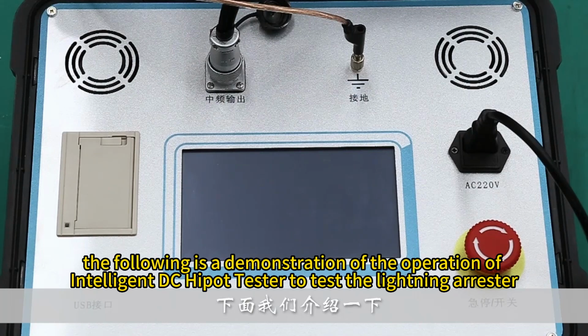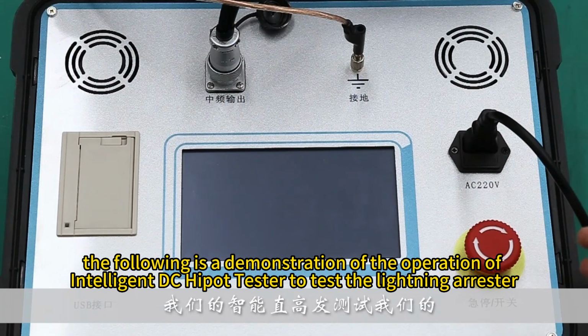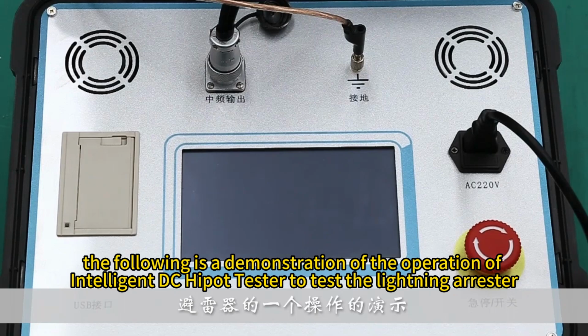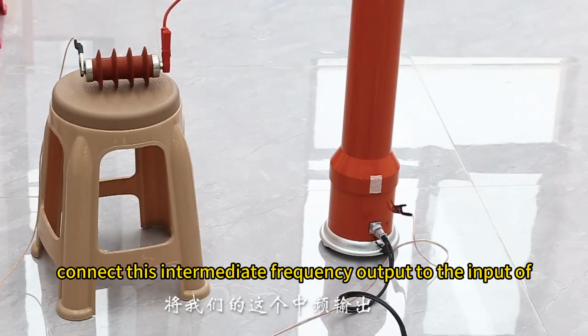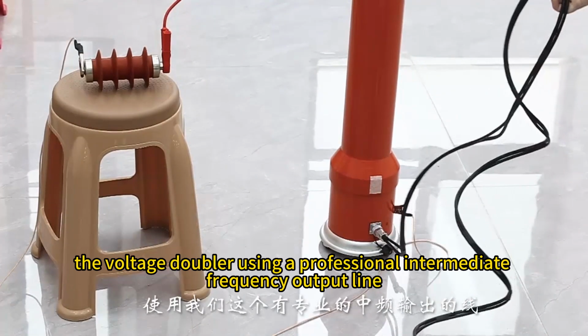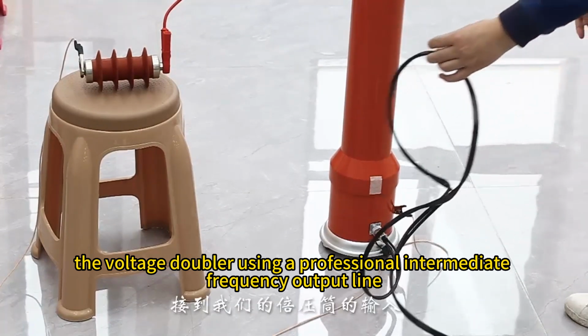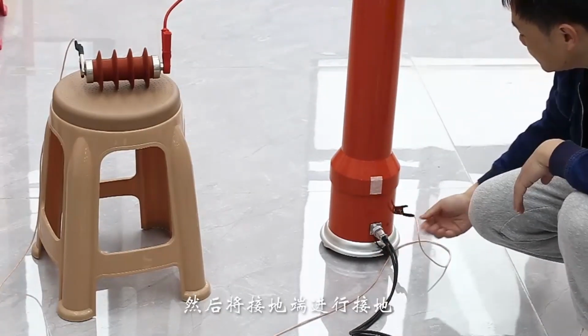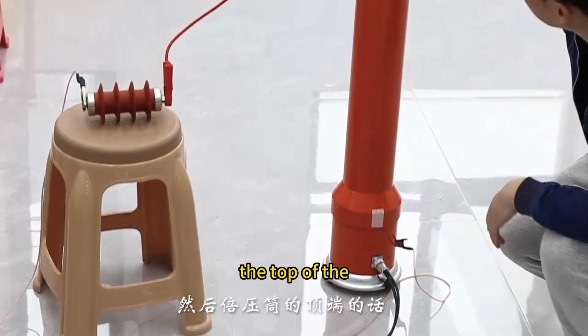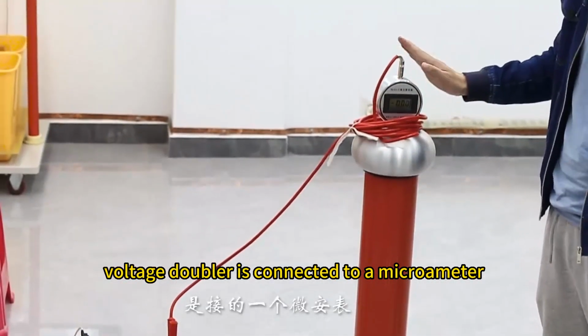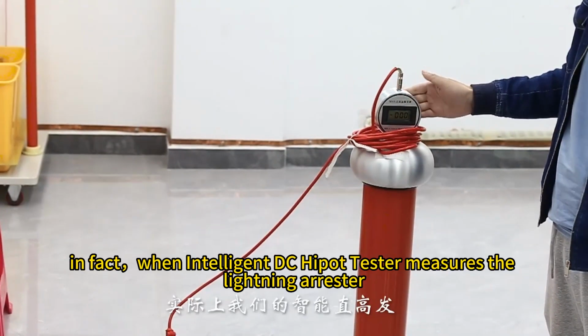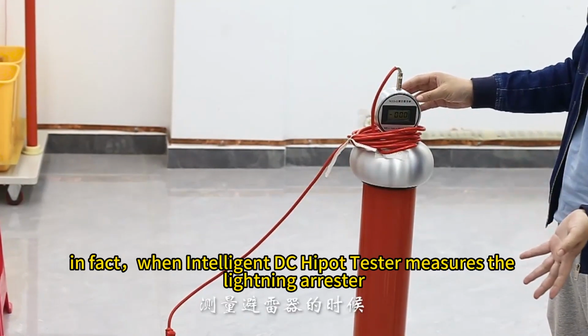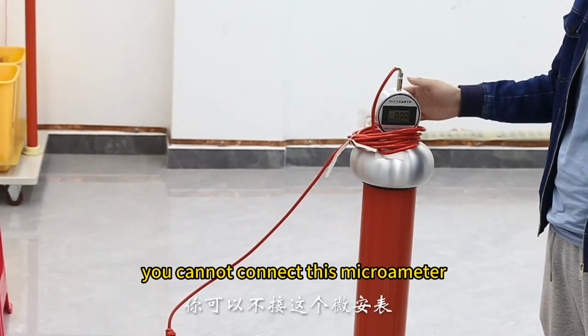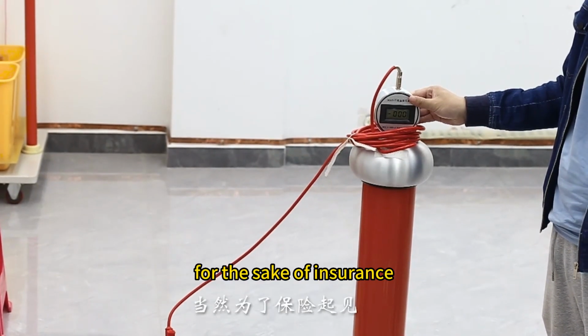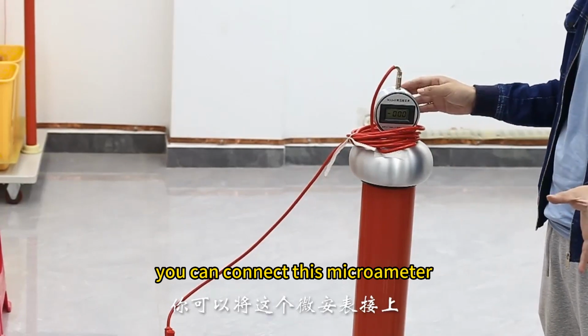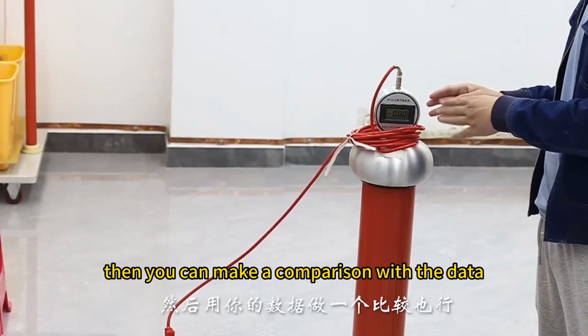The following is a demonstration of the operation of the intelligent DC Hipot tester to test the lightning arrestor. Connect this intermediate frequency output to the input of the voltage doubler using a professional intermediate frequency output line. Ground the ground terminal. The top of the voltage doubler is connected to a microammeter. In fact, when the intelligent DC Hipot tester measures the lightning arrestor, you do not need to connect this microammeter. For the sake of insurance, you can connect it. Then you can make a comparison with the data.